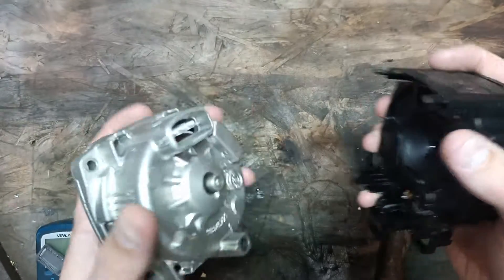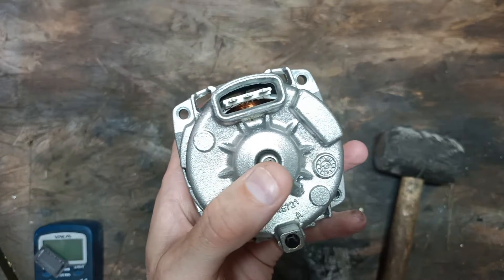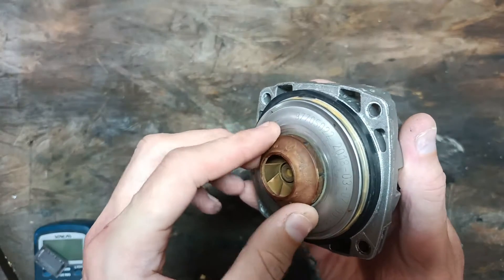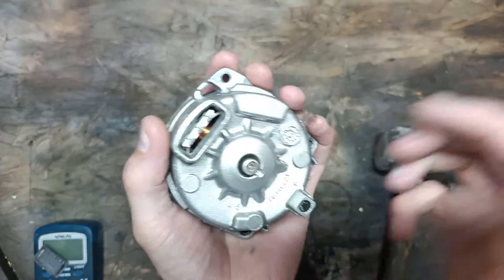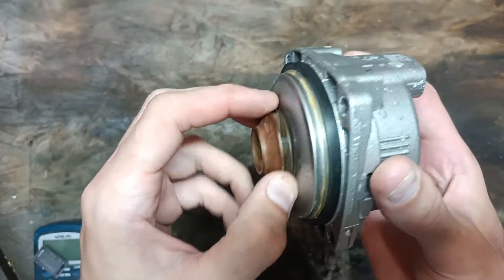What they say is put a screwdriver through and then do that. The problem is they've made a really poor design here because the screw is made of mild steel and it's not very good. If the pump is seized solid, what good is that? You've got to really put pressure on it, and if it wears away, what's the point? You need a good screw that can really move this thing.